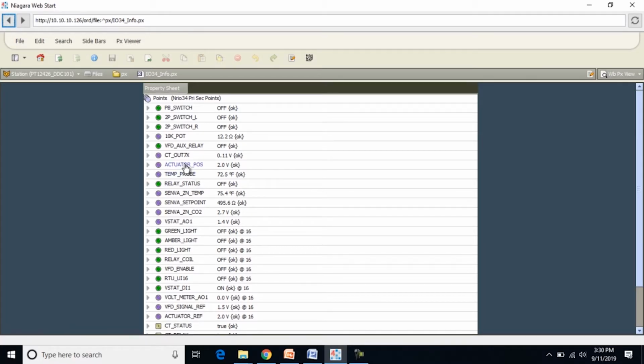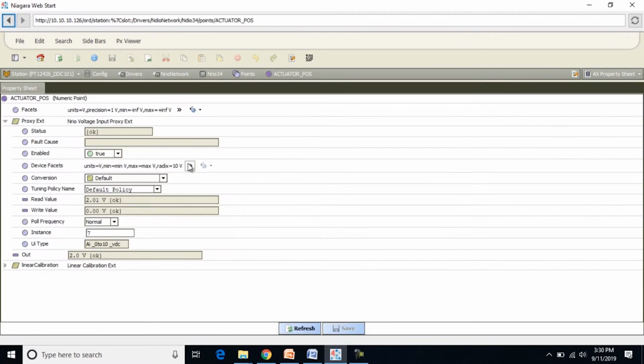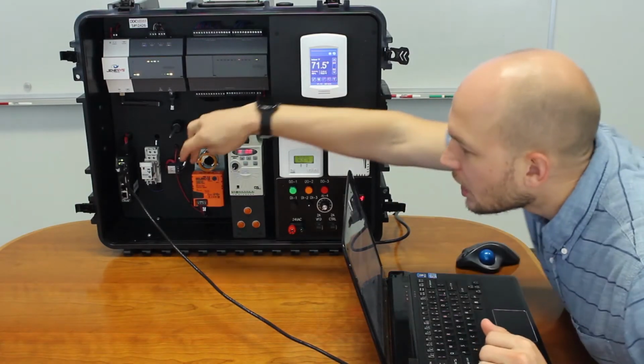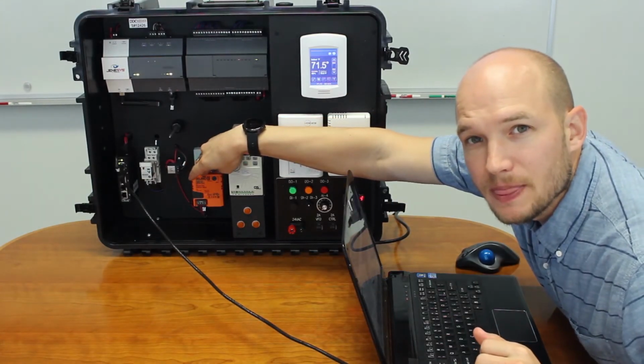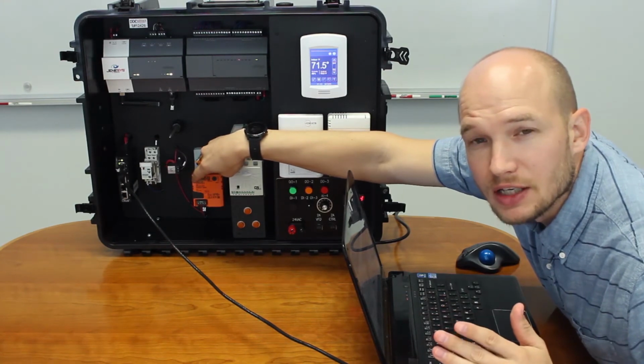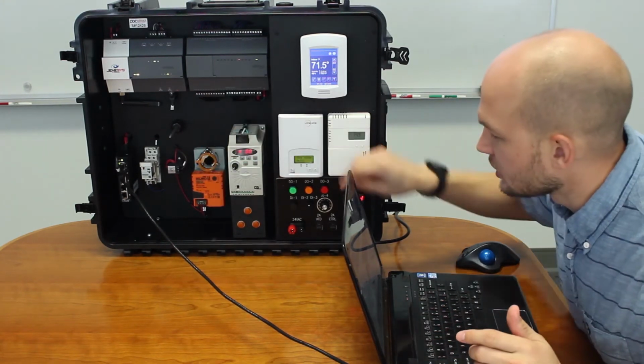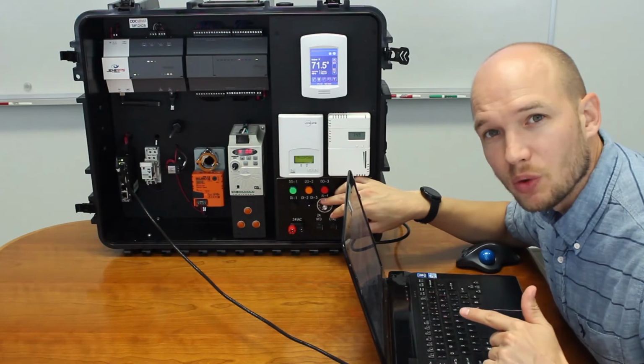The next analog input we're going to look at is the actuator position. This is a voltage input, conversion's default, current read value is 2 volts. If you remember, this orange actuator is a 2 to 10 volt system, so I'm going to adjust it to open it up and we'll see what the voltage does.